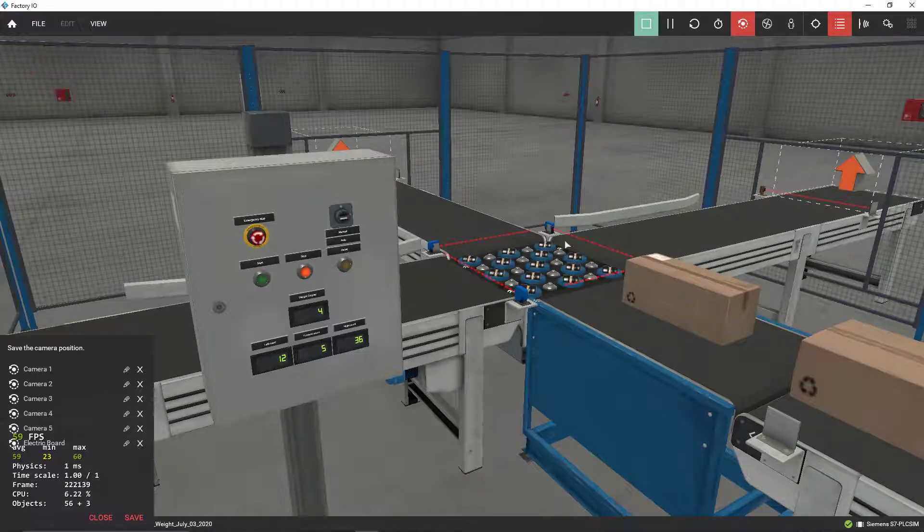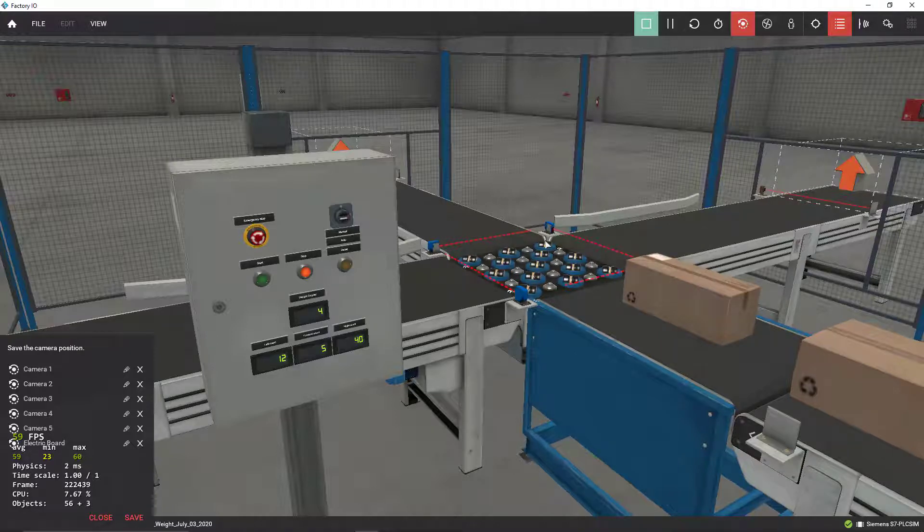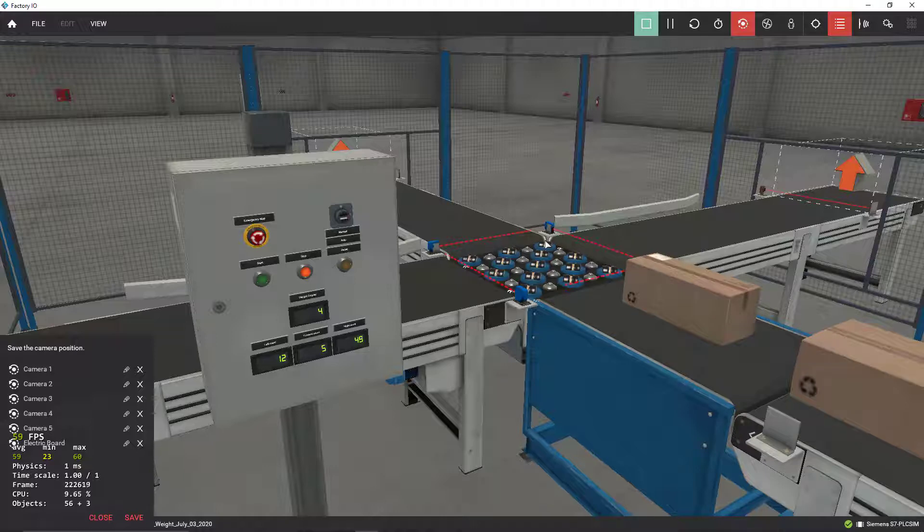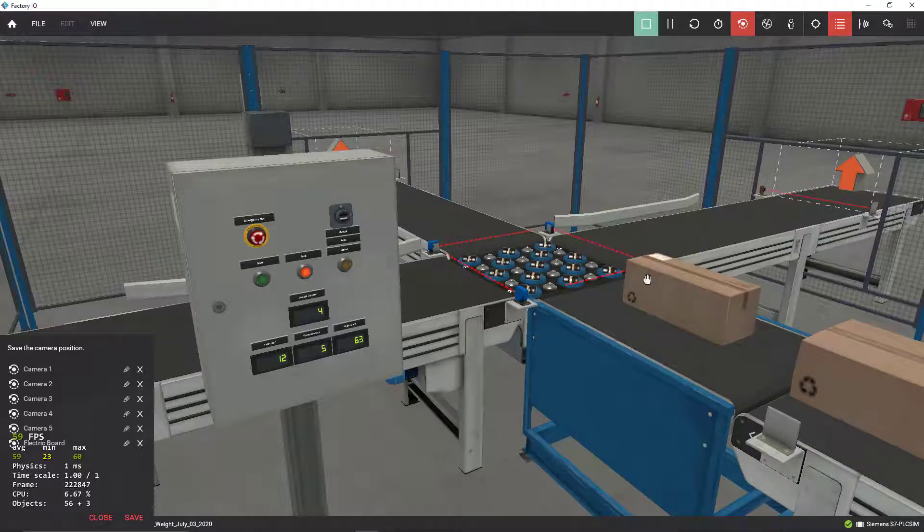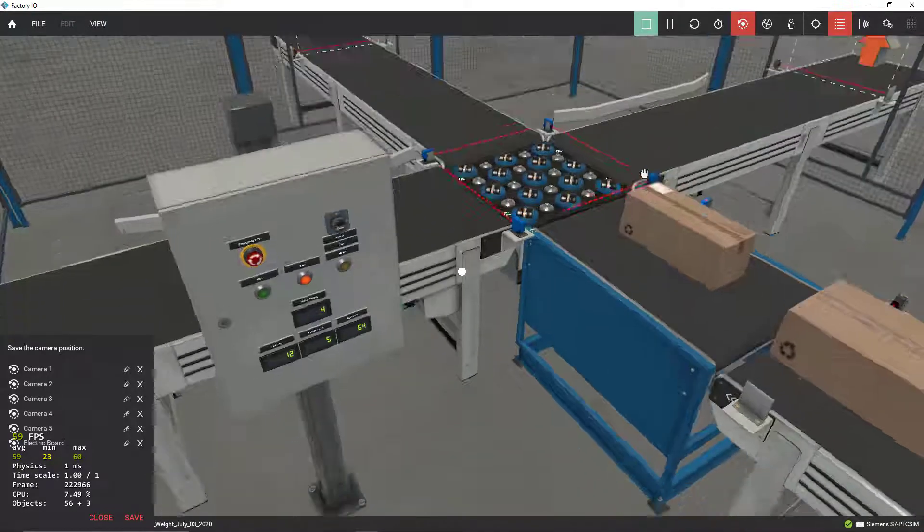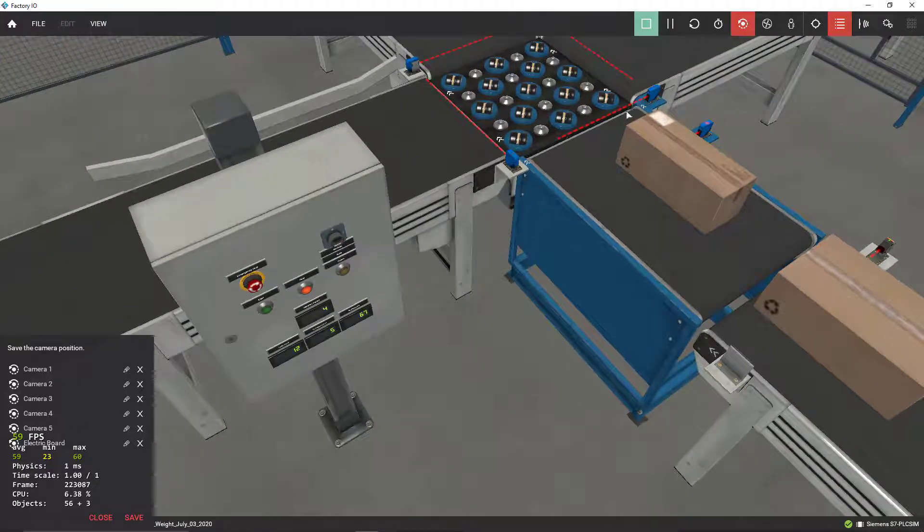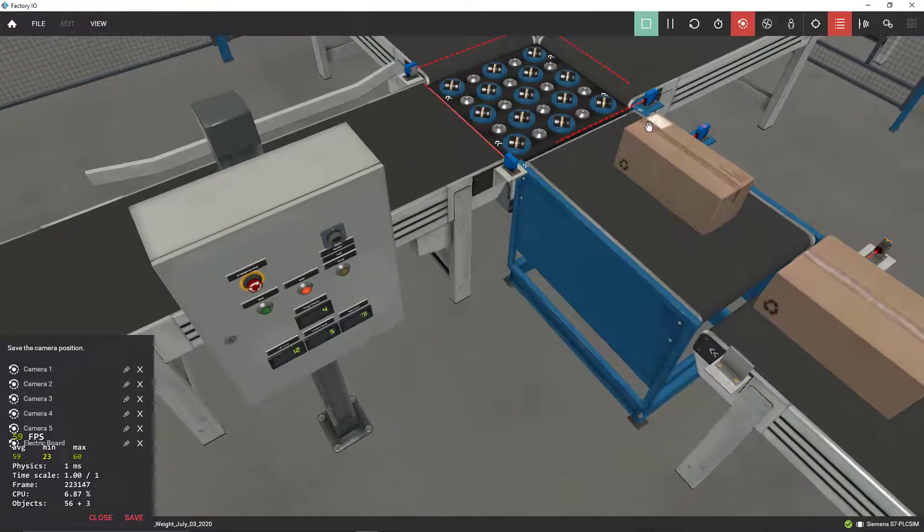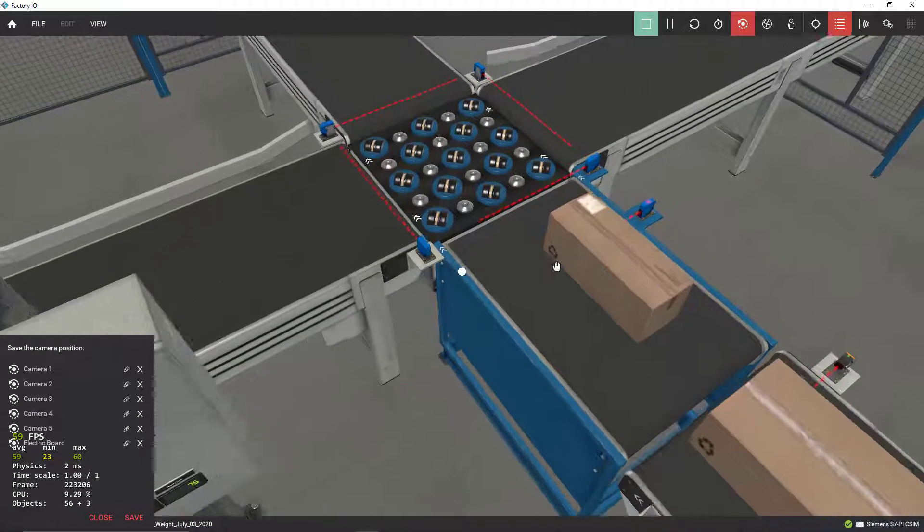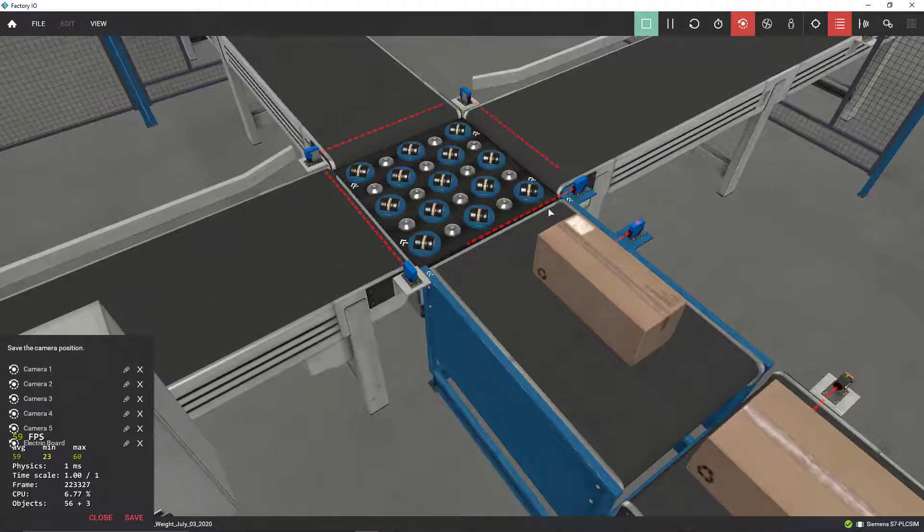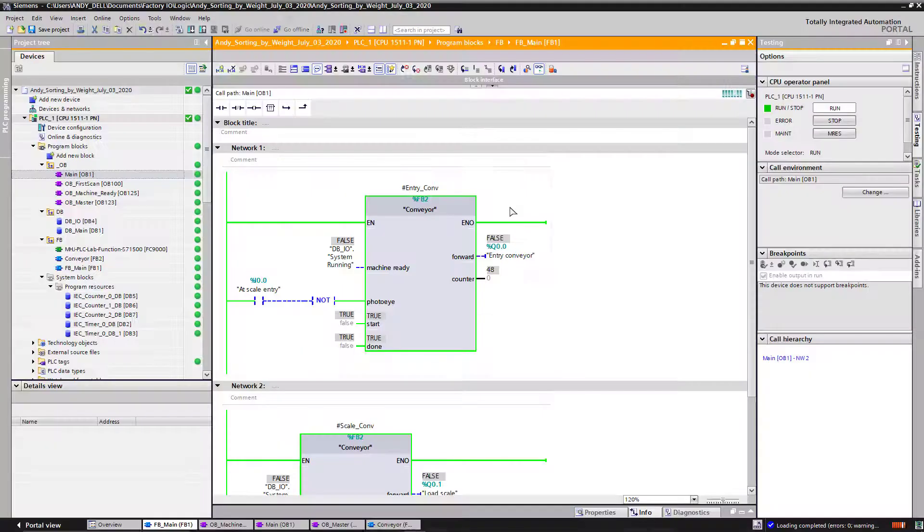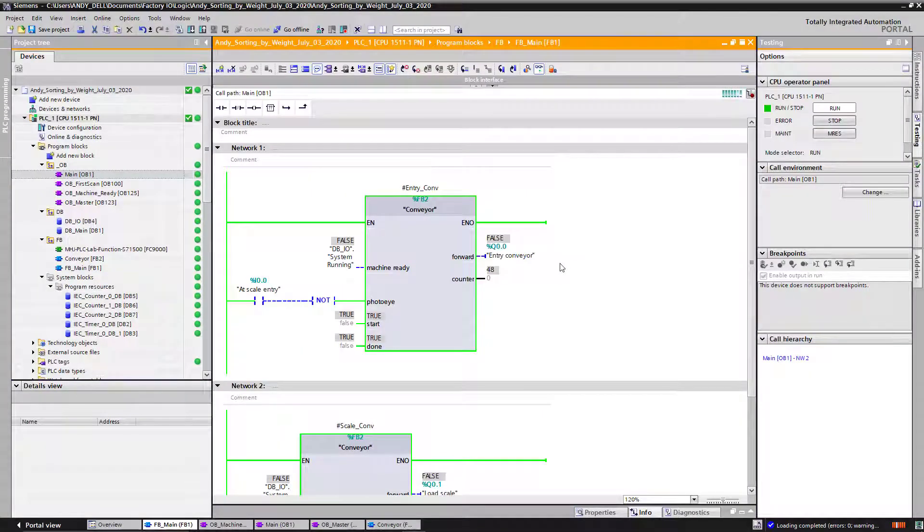So these conveyors, all three of them, to save energy I shut them off completely after 10 seconds of inactivity. If I don't see any boxes going through this sensor over here, the photo eye, in other words, if the photo eye is not detecting boxes going through, I just shut off all conveyors.